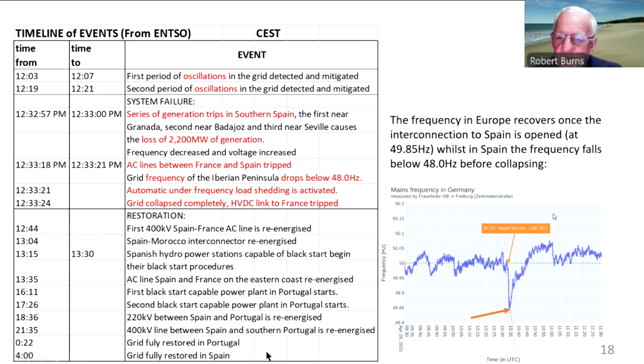Now, if you look over here on this little graph, this is the frequency of Europe, but measured in Germany. And of course, Spain is connected to Europe before the event, so it's experiencing the same sort of frequency fluctuations. Now, they've put on their little graph grid separation there. Well, it's not. That's the start of the events. That's the first tripping there. And what happened? The frequency started to fall.